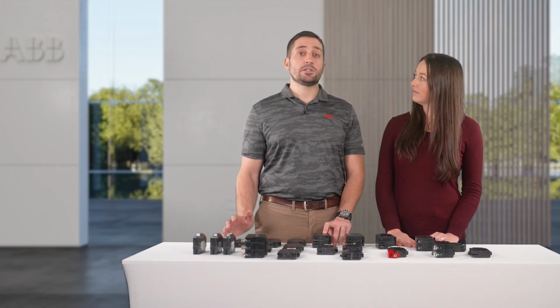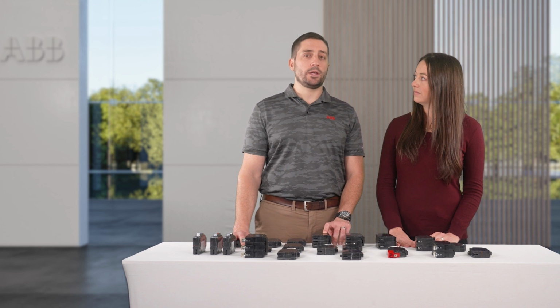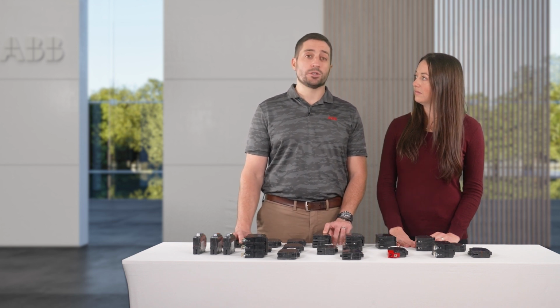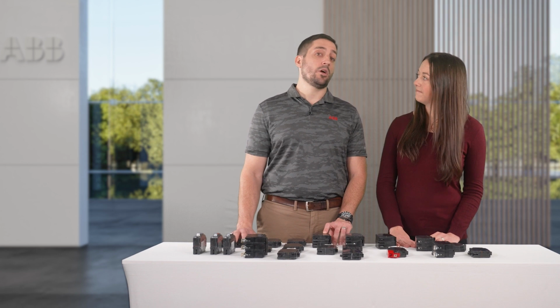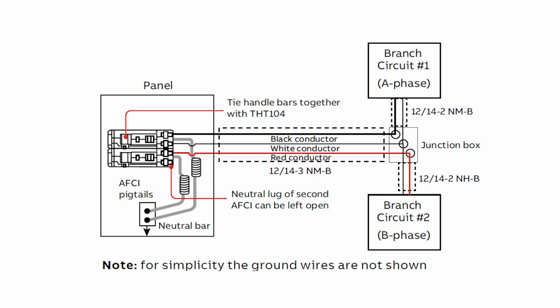Multi-wire circuits and shared or mixed neutral installations did not work easily with arc fault protection, requiring hours of tracing neutrals to install the new arc fault breakers. When arc fault circuit interrupters were introduced in response to the NEC requirements, the new technology monitored the complete circuit. This meant the hot side and the neutral side needed to show no signs of potential arc fault events, usually the result of deteriorated wires, poor connections, or installation breaches. To achieve this, arc fault circuit interrupters incorporated some level of ground fault detection and, as such, needed a dedicated neutral path back to the breaker to avoid nuisance tripping.